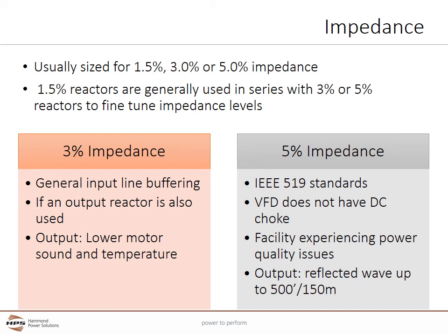Select 5% impedance as part of a solution to meet IEEE 519 harmonic standards and when a VFD does not have a DC choke. If a facility is already experiencing power quality issues, 5% should be considered. 5% is a good choice on the output to mitigate the reflective wave issue up to 500 feet or 150 meters.